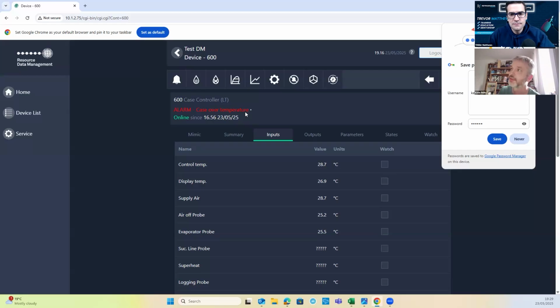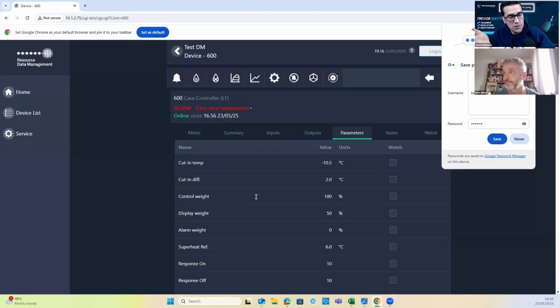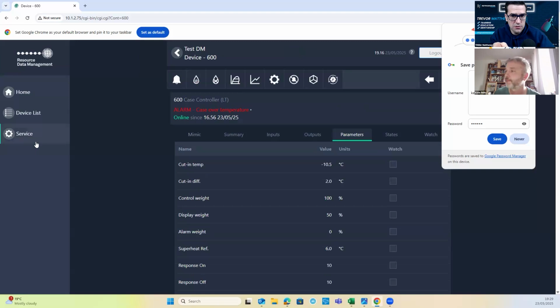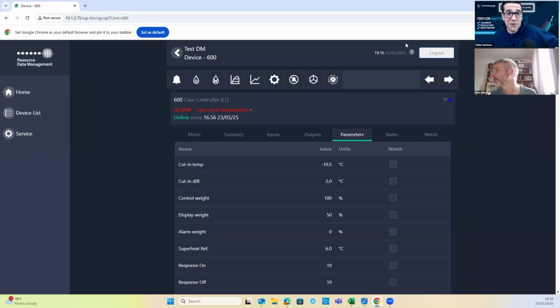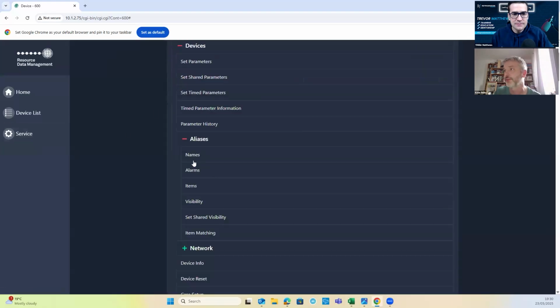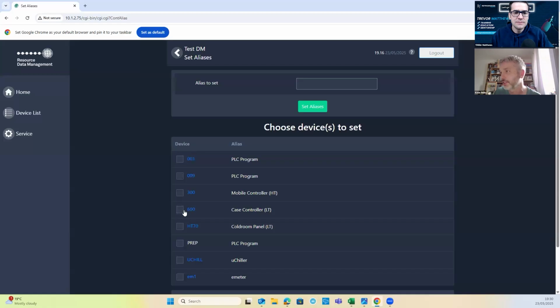And that's potentially confusing. I can also set the name of this fixture in the panel, which I would obviously do. I would set it to what it is. If it's a meat case, I set it to meat case. If it's a produce cold room, I'll set it to be a produce cold room. And that's very important on the startup, so that technicians know. You just close the save password. Very important. So when you go into that store and it's meat case, you know you're going down to the meat, not the produce. Yeah, and it's worth bearing in mind if you change a controller and it comes back up case controller HT or LT or whatever, all you've got to do is go aliases, names, find your device right there, and we can change it to be whatever we like.